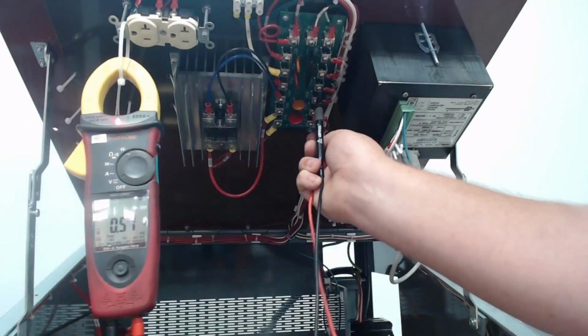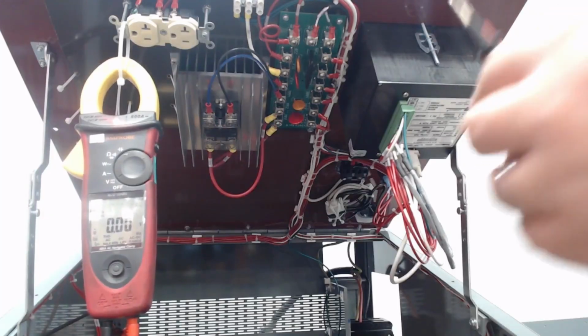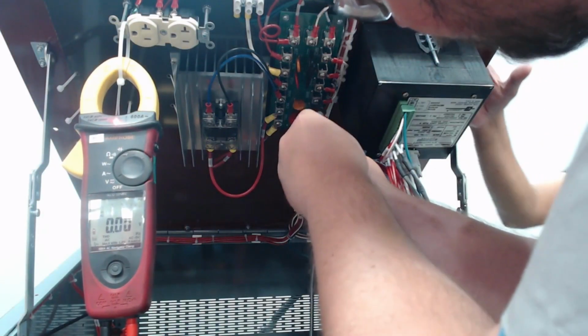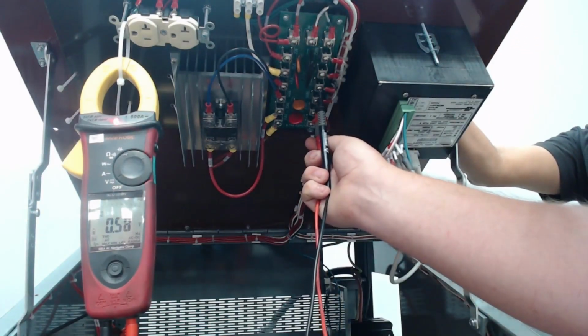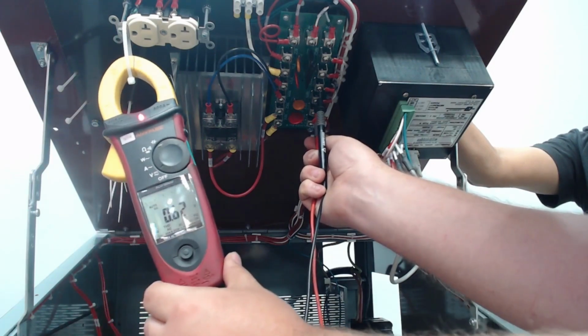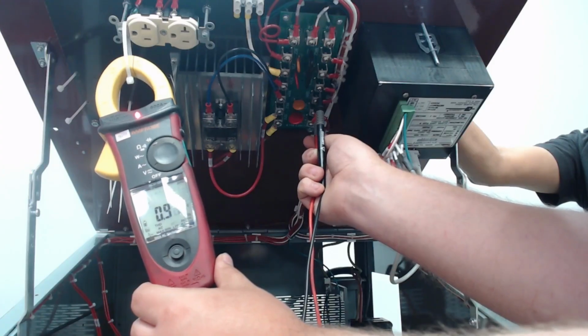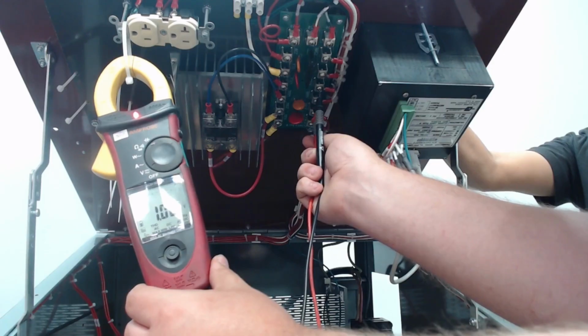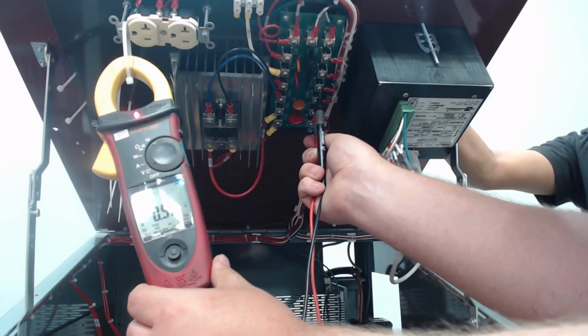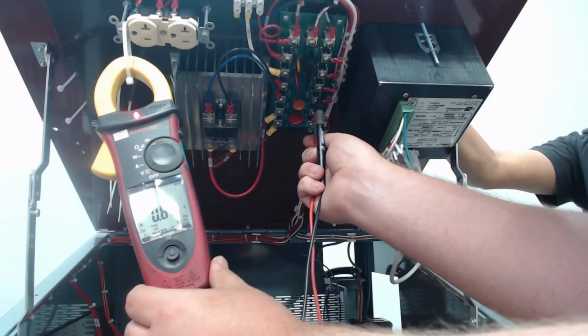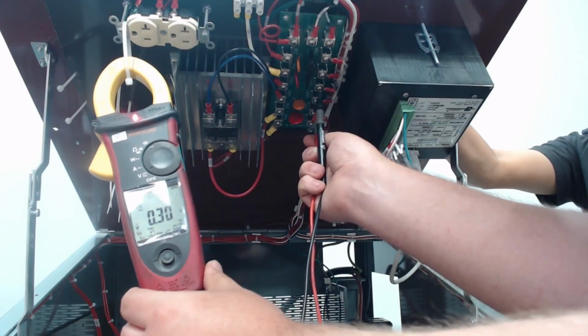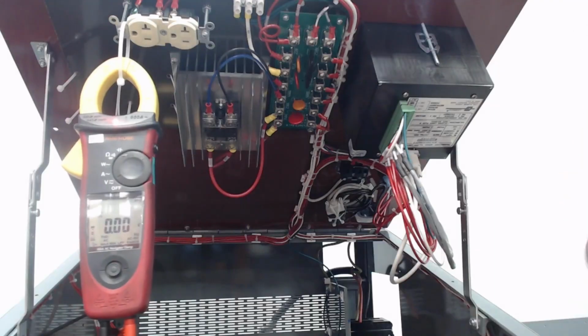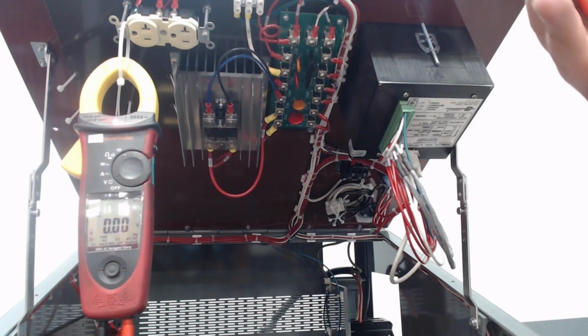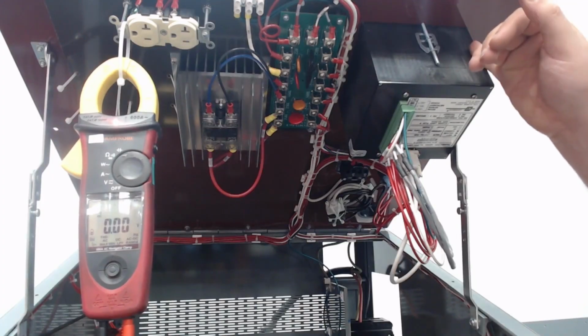As you hold the up arrow, that's just going to slowly increase the voltage. Omar, if you would, please go ahead and hold the up arrow as I reconnect that. All right, you're good. If you hold the up arrow. All right, if y'all can see that, it's slowly going up. That'll be fine. Will you hold the down arrow now? All right, thank you. So that's basically that meter working. We know the up and down arrows work if you're getting that volts DC change. I will mention polarity matters, so it needs to be positive. If it's negative, it won't work. So we know that the meter is good at this point.